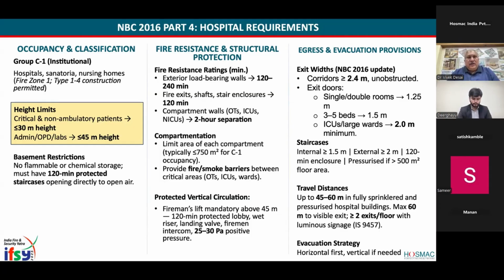Then in terms of vertical circulation, if a building is more than 45 meters, and there are a lot of hospitals now going more than 45 meters in various cities, then a fireman lift is mandatory. You need to have a lift which will be used only by the firemen, at a certain positive pressure. Satish, can you talk about that? I don't know, this 25-30 Pa positive pressure. Yeah, so the lift lobby has to be maintained at 30 Pascal pressure, whereas all the staircases, the lift pit and the lift well have to be maintained at 50 Pascal.